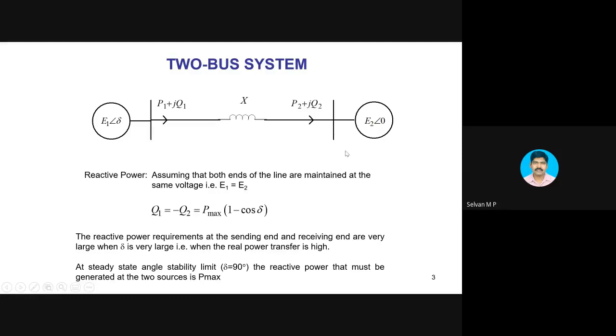I may have any other device to give me reactive power that is flowing into the line. So at both the ends, reactive power is flowing into the line. Interestingly, the real power flows from sending end to receiving end. There is no change in the direction of real power. This also you have to understand. We can have different directions for real and reactive power in the same conductor. Okay? In the same conductor, because real and reactive power can be decoupled, you can see that real power flows in one direction and reactive power flows in the other direction, though the AC current flows in only one direction. It flows from this bus to this bus, but the power flow may be different, right?